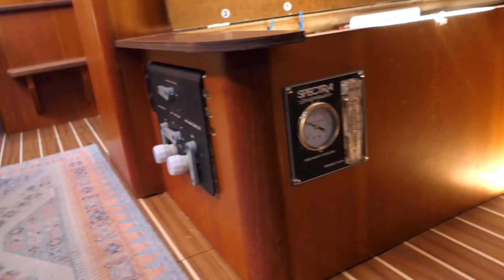I've had everything up and running for a few minutes, and fixed a minor hose leak. You really have to crank the hose clamps down like crazy on this stuff, because even the low pressure side is pretty high pressure. With both pumps combined, we're getting right about 13, almost 13. Here's our old pump, the one that was better before—that's pump 2. With just pump 2, we're getting right about 7, which is just a little shy of what it's supposed to do; they're supposed to do about 7.5. Now if you switch to pump 1, with the new pump head, this one's crushing it—we're getting like 8, just a little over 8.